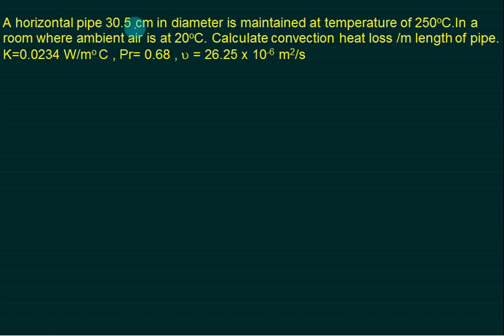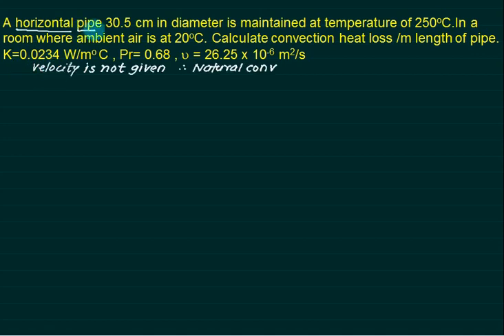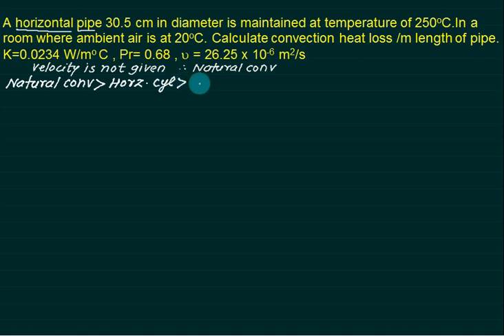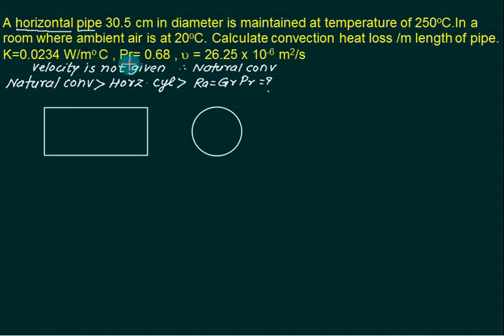Example 1: A horizontal pipe 30.5 cm in diameter is maintained at 250°C in a room where ambient air is at 20°C. Calculate convection heat loss per meter length of pipe. Since no velocity is given, this is a natural convection problem. The geometry is a horizontal cylinder, so we need to find the Rayleigh number (Gr × Pr). For a horizontal cylinder, Lc = diameter = 0.305 m.